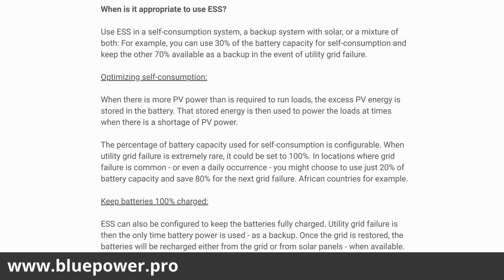And when is it appropriate to use ESS? So ESS is a self-consumption system, a backup system with solar, or a mixture of both. For example, you can use 30% of the battery capacity for self-consumption and keep 70% available as backup in the event of utility grid failure.